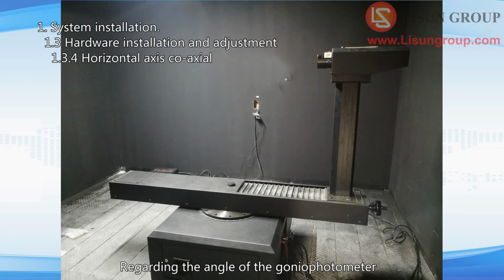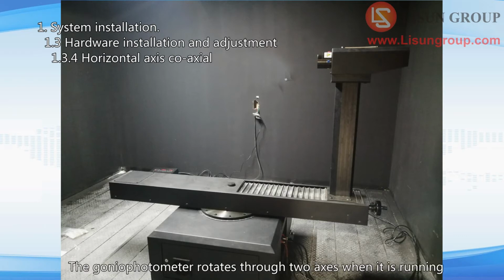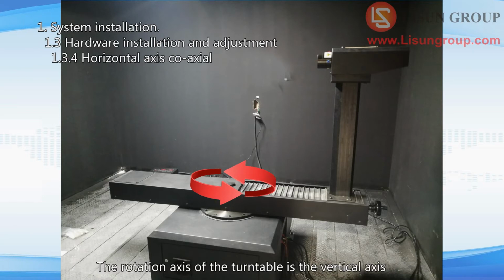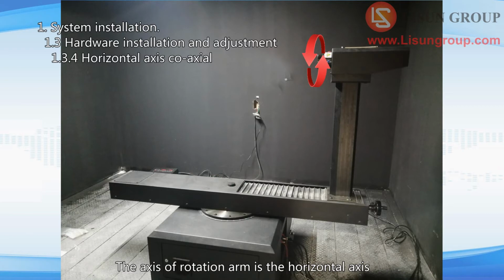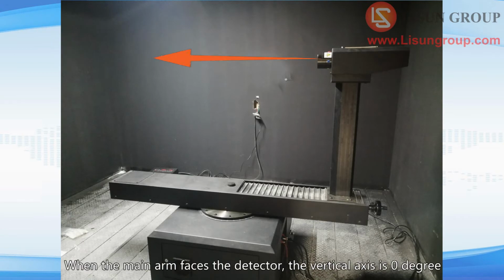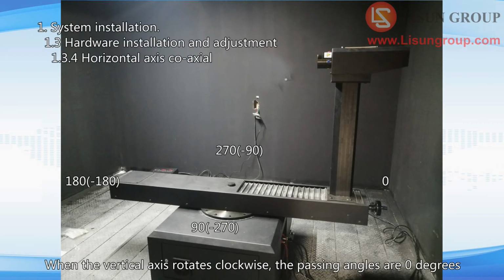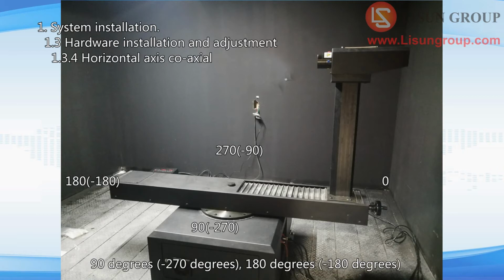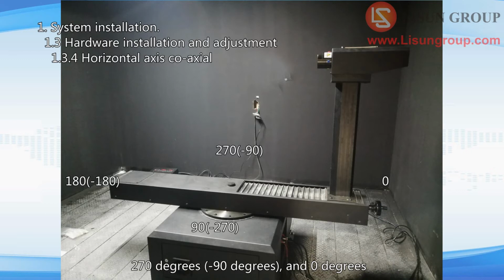Regarding the angle of the goniophotometer, the goniophotometer rotates through 2 axes when it is running. The rotation axis of the turntable is the vertical axis. The axis of the rotation arm is the horizontal axis. When the main arm faces the detector, the vertical axis is 0 degrees. When the vertical axis rotates clockwise, the passing angles are 0 degrees, 90 degrees, minus 270 degrees, 180 degrees, minus 180 degrees, 270 degrees, minus 90 degrees, and 0 degrees.